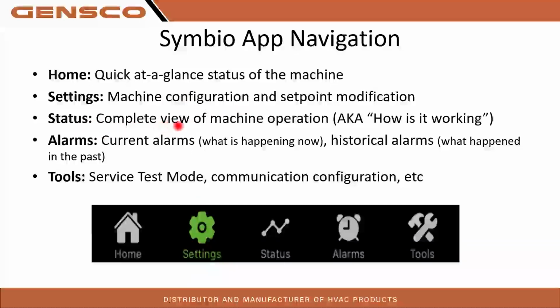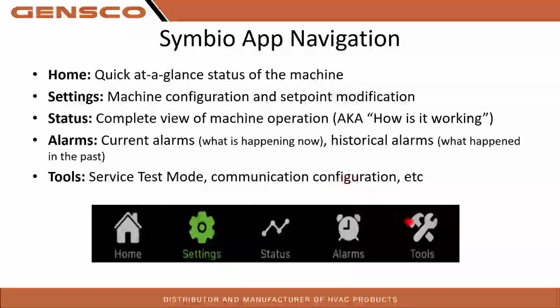Here's our status. So complete view of the machine. We can't change anything, but how is it working and what are we calling for? Of course, current alarms, what is happening now, and historical alarms. Is it critical? Is it yellow? It'll still operate, but it needs attention. Tools. We use tools quite a bit with service test mode, which I love this service test mode. There's no more running up and down or adding jumpers. That service test mode, keep in mind, does override a 5-minute wait time. So you can slam it into heating and cooling pretty quick. So watch your pressures. Communication configuration. We go inside tools too to see what is communicating, which is pretty important if we have multiple control boards in there.